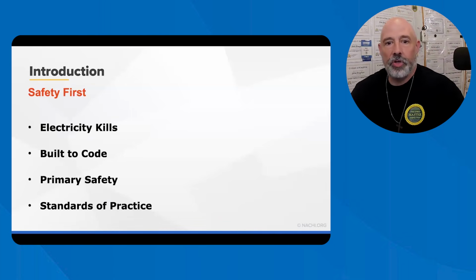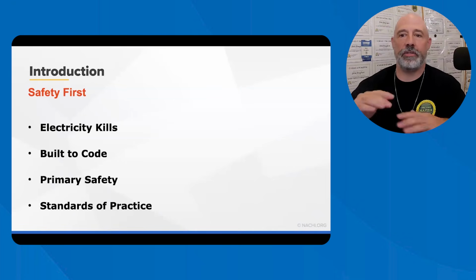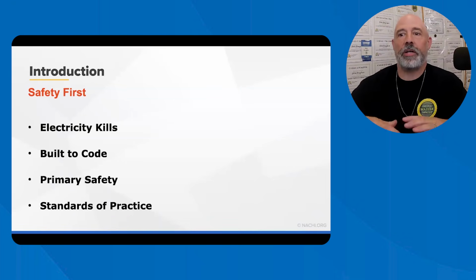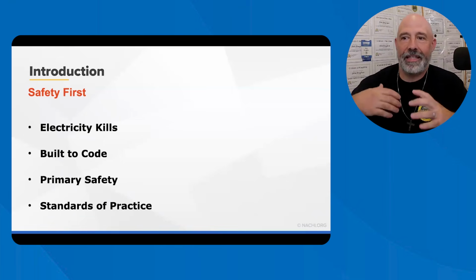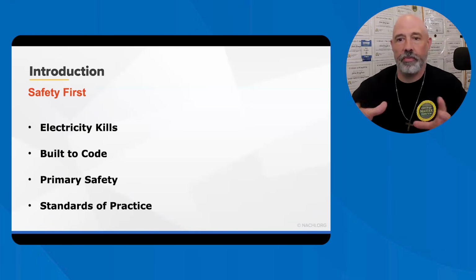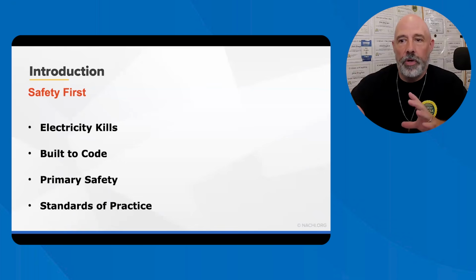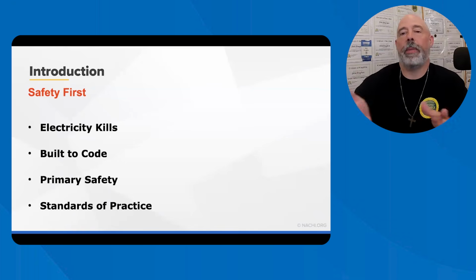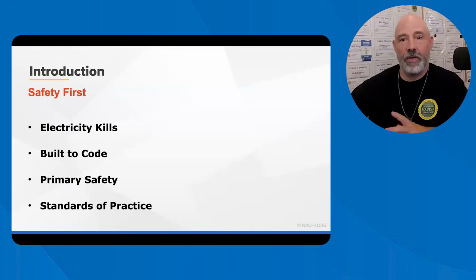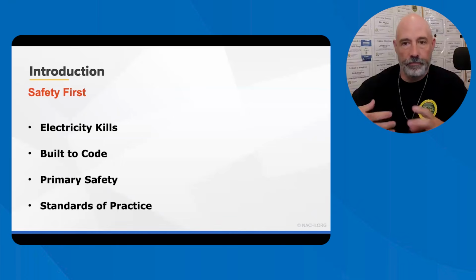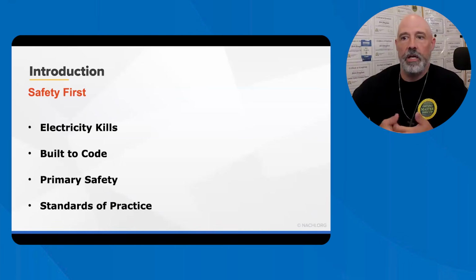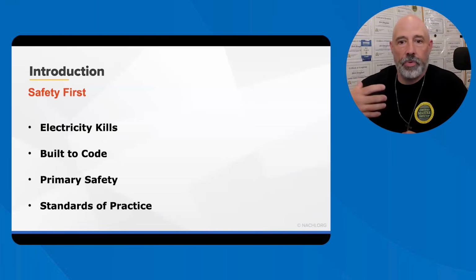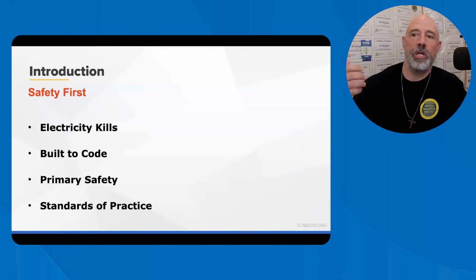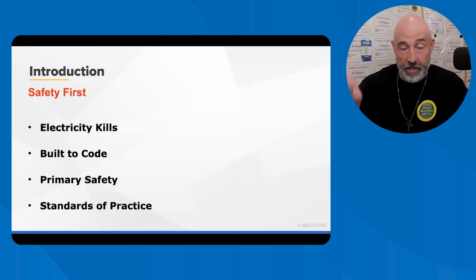And built to code. This is one of those few areas that is very gray, where most inspectors would report a system or component as in need of correction. But it might have been built to code when the home was built, and today the standard says that it's unsafe. So you have to understand where things are. The absence of GFCI protection in the kitchen, for example, would fall into that category. Many home inspectors might put that in as in need of correction, but the house was built in 1940, so you're not going to see that.